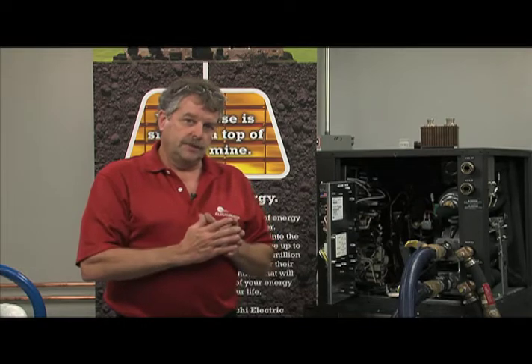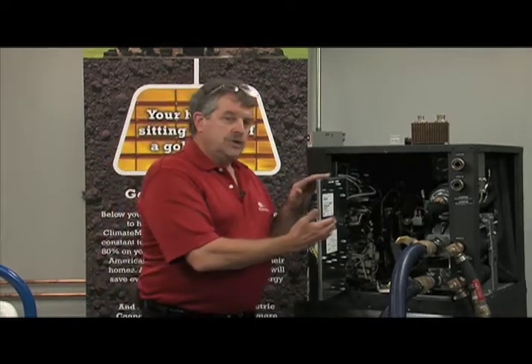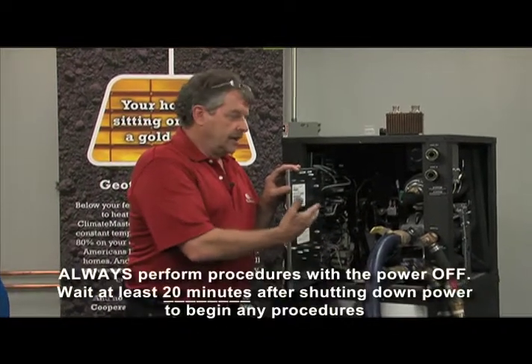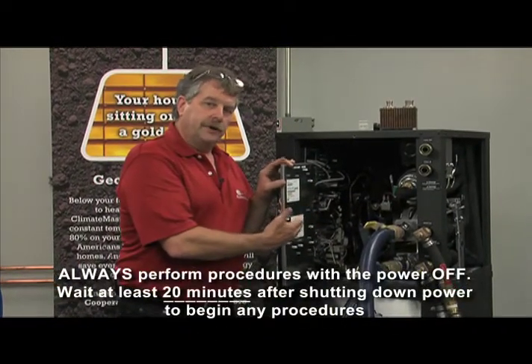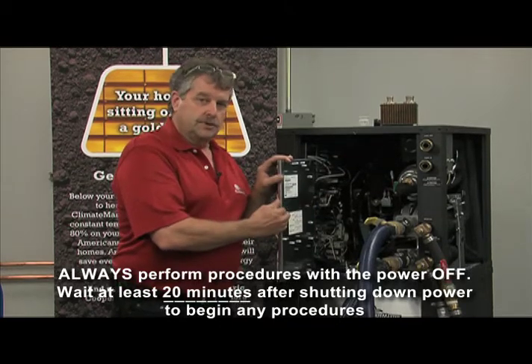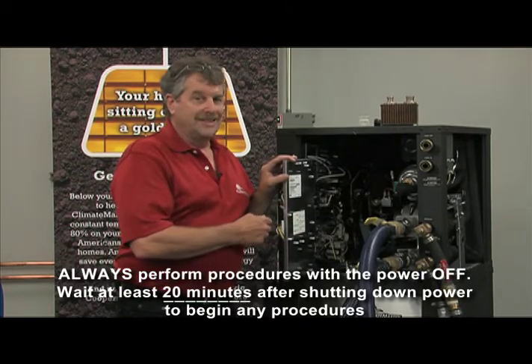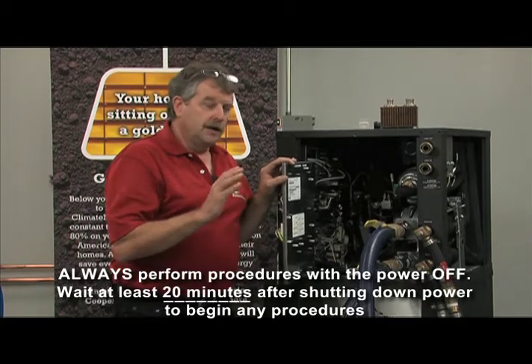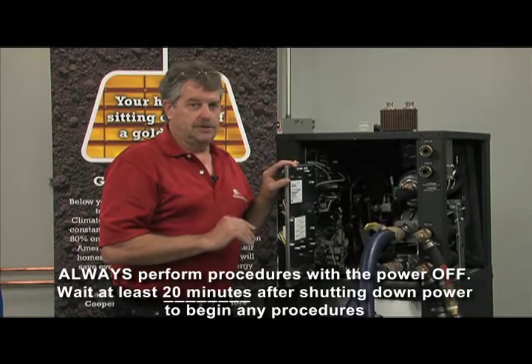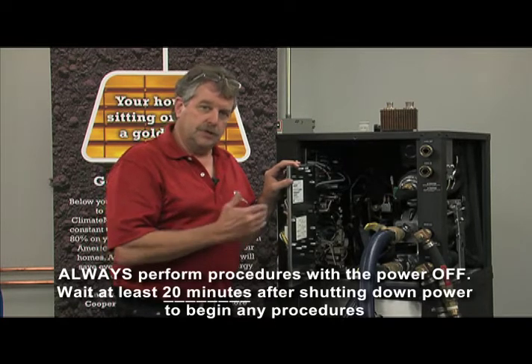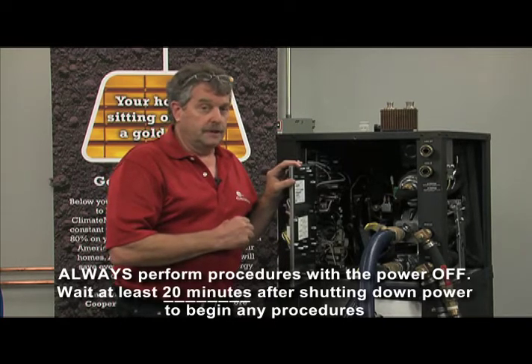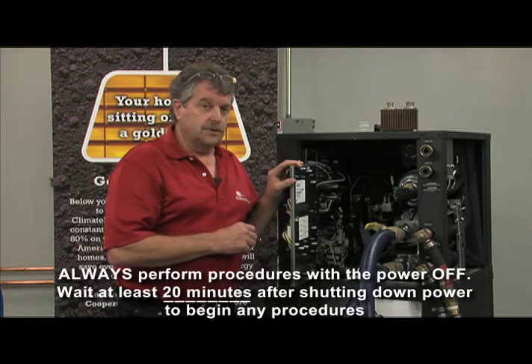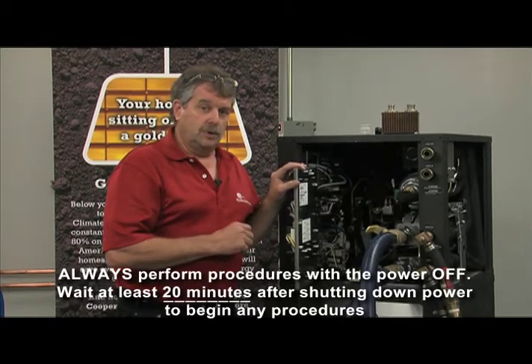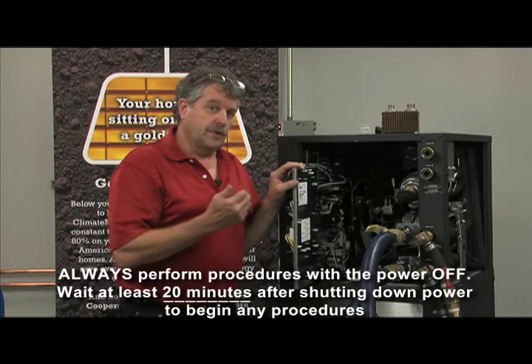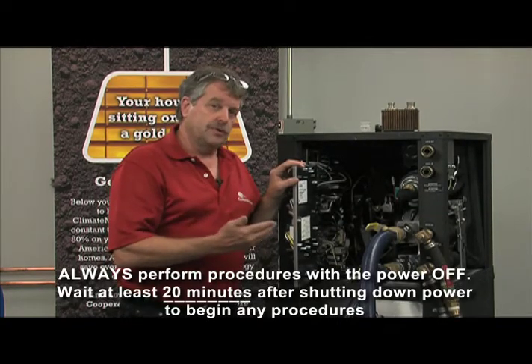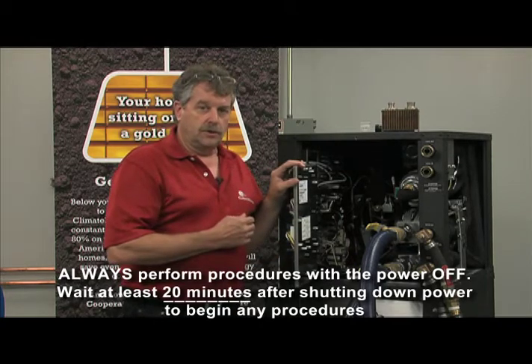But first of all, guys, let me reference that you should always do flushing on our product with the power off. And if it happens to be the Trilogy, as with this example, you want to make sure that power has been off at least 20 minutes. Don't hurry that. Don't shortcut that, because you won't like the sting and the bite that you get by reaching in next to that high voltage. We have a number of capacitors and an off-board inductor. They pack a wallop, and it takes quite a while for them to discharge. So again, it's important that you make sure that 20 minutes has transpired with no power before you start to tackle anything here on the wet side.